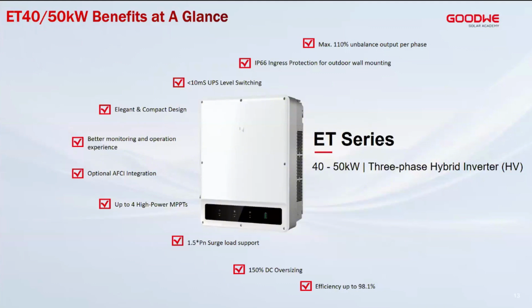The inverter itself has improved the monitoring and operation experience. If you look at the inverter, it has LEDs at the front, and coupled with the EasyLink, we have a communication module, which I will also introduce to you. You can connect to it either wired through the LAN cable, wirelessly, or even by Bluetooth, just to set up your system and monitor the product itself. You can also connect it wirelessly to the internet so that you can set up a monitoring plan for better historical data monitoring of the system itself.